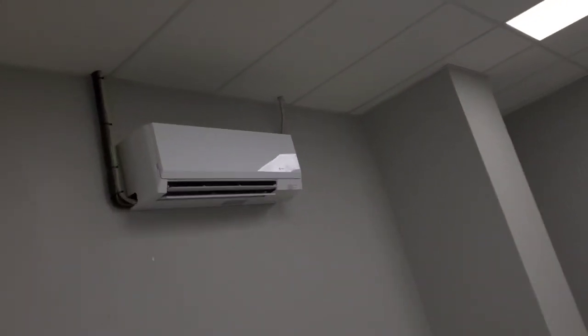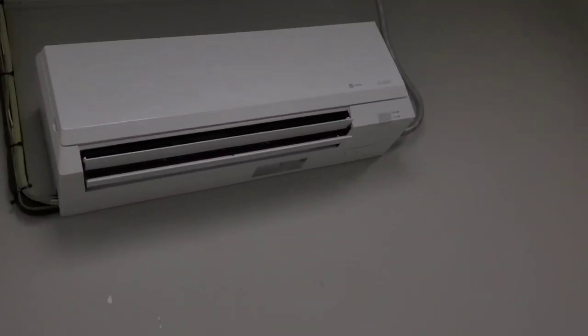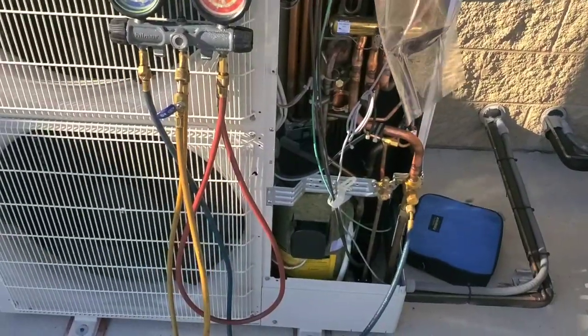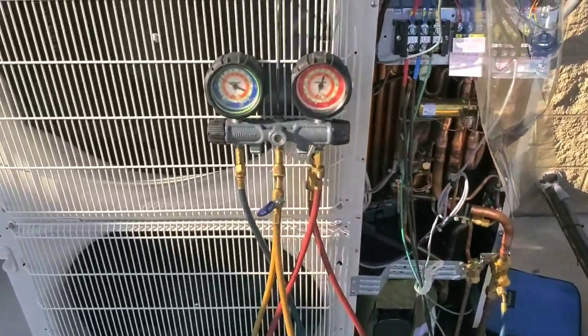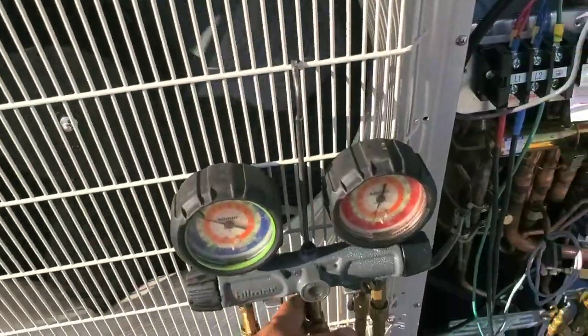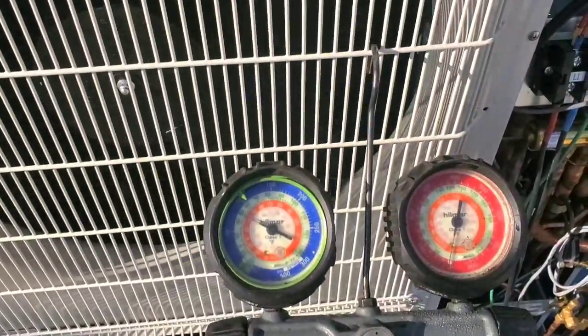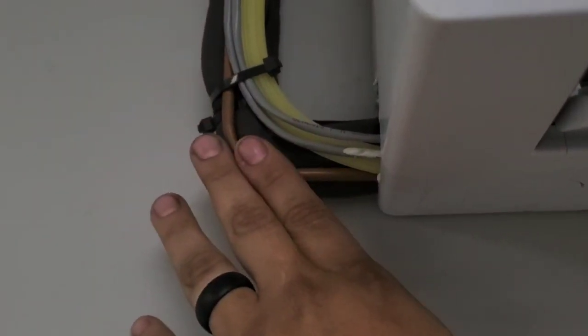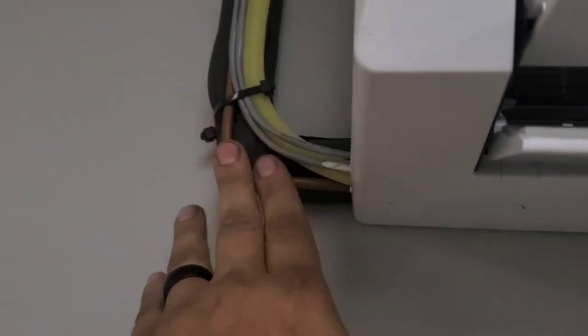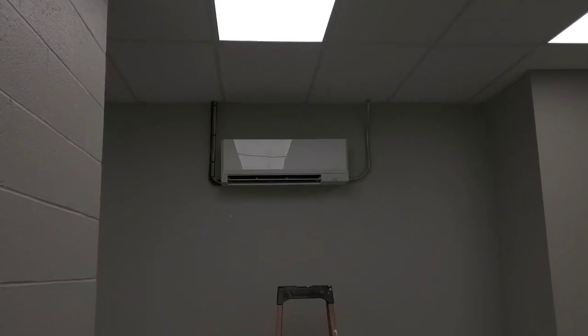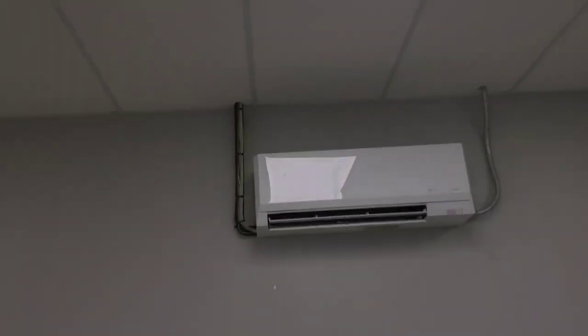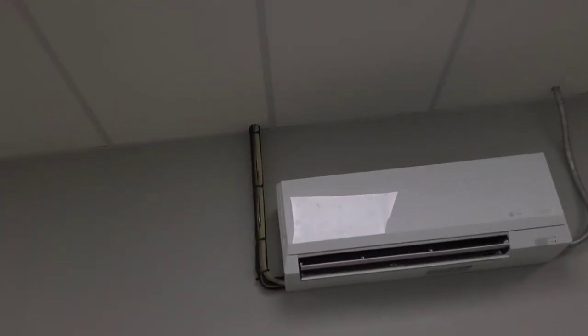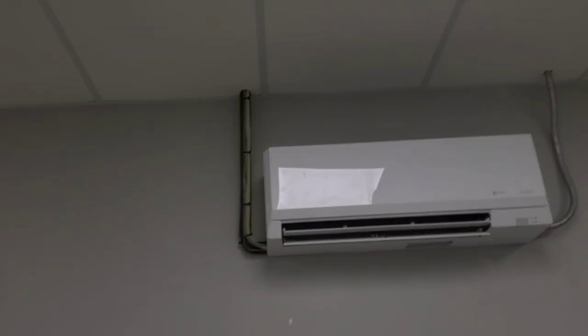Starting to cool off there. You know, they put the ceiling tiles up yesterday. They waited till today. They've been doing it in the air conditioning. Starting to ramp up compressor speed. Hasn't raised the suction pressure yet. Stands to reason it's going to start feeding more. When they called for uninsulated liquid line, seems like they didn't count on it being cold. Maybe it won't sweat. The ceiling tile dudes put the hole in the ceiling tile like a quarter of an inch too far to the right, and now my line set's crooked.